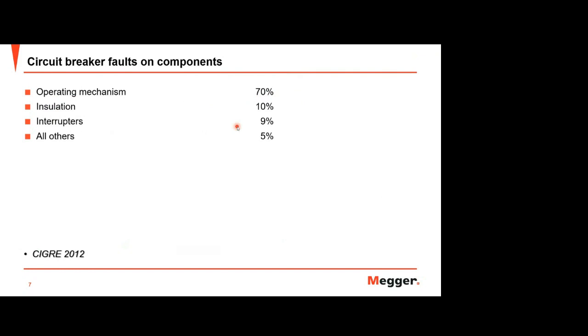So this is based on the CIGRE 2012 report. Even though many circuit breaker manufacturers now improve the reliability and the quality, so maybe it is no longer valid, at least it still gives the higher percentage. Maybe the percentage number is not correct like this, but at least it is still higher compared to other component issues.